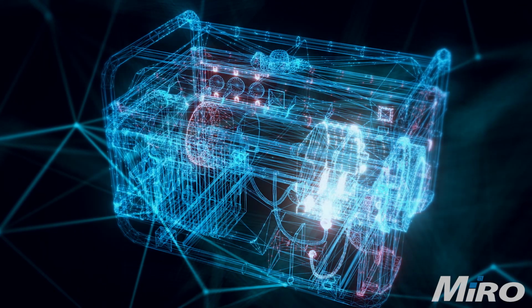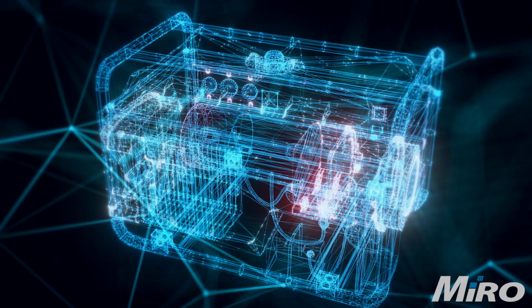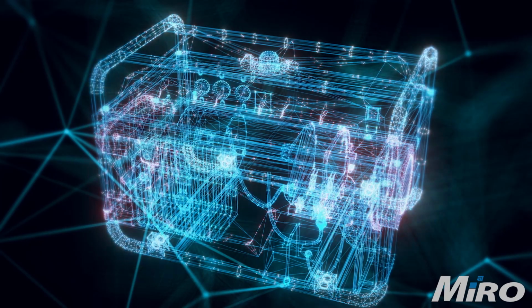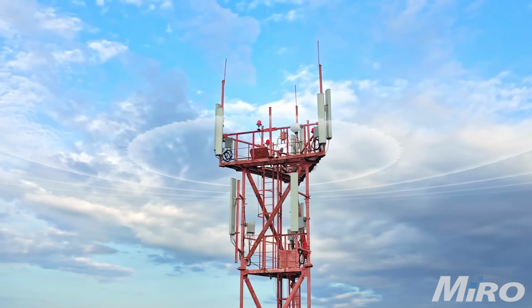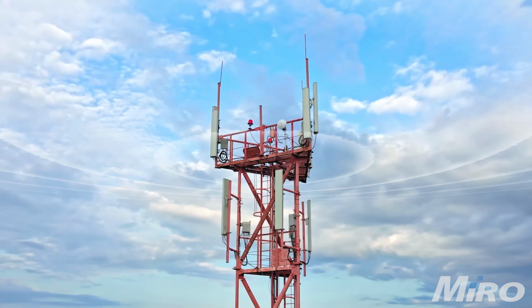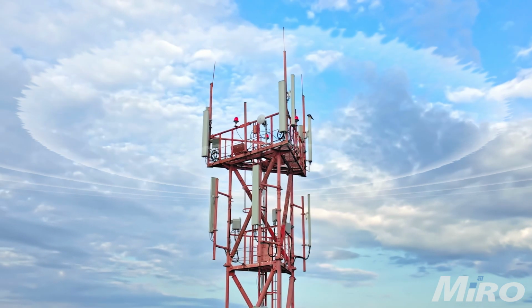A superior solution to this would be a generator backup coupled with a traditional UPS. Here, the grid powers the high site under normal power situations and then charges the UPS's batteries. In case of power failure from the grid, the UPS takes over without any disruption to the equipment and will do so long enough to allow the generator to start up and stabilize the power output before switching over to the generator supply. While this is close to being the perfect combination for power deliveries for a high site, it does present some unique challenges.